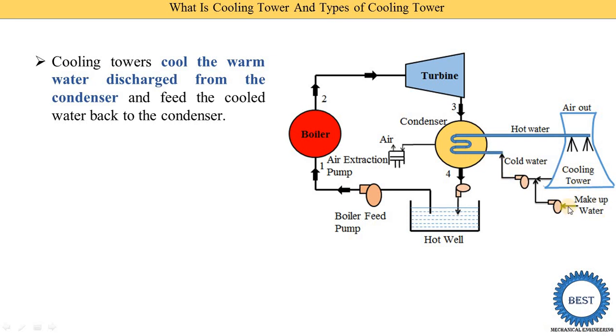We also need to add some makeup water because some quantity of water particles or steam escapes to the atmosphere with the air. That is why we need to add 3 to 5% makeup water to the cold water.